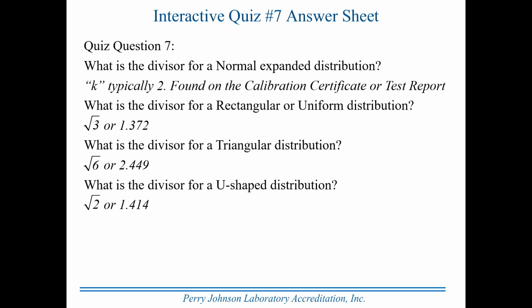So you get a lot of values there at the low end, and then it's accelerated as it heats and drives it back up toward the high limit. And as it approaches the high limit, the heat shuts off and the air comes on, starting to drive it back down. So you get a concentration of measurement points at both extremes and a reduced number in the middle. You get some as it's traveling from one extreme to the other, but you don't get many. So consequently, it's U-shaped. Now remember, associate that with boundary-driven heating and cooling system.